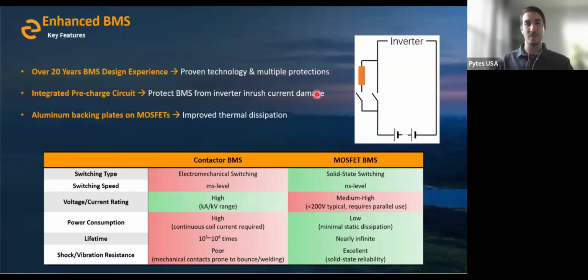Another really important feature that we've added to the V10 is a pre-charge circuit. This is an additional level of protection, not just for the batteries, but for the BMS in general. Backing up a little bit, when you connect a battery to an inverter, say that inverter has not been energized before, so we haven't connected it to the grid and we haven't connected it to PV. This is a brand new install you're commissioning for the first time, and the batteries are the first thing that power it up.